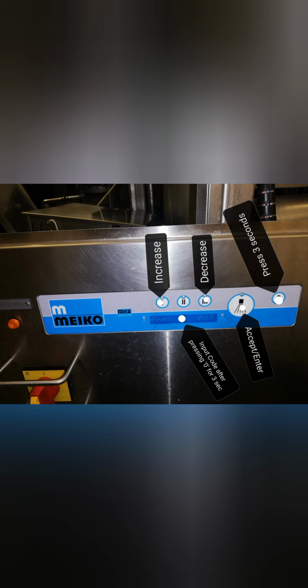So all you have to do is switch on your machine, wait until the first flush, press the 0 for 3 seconds, then choose the code. Since I want to modify the configuration, I put in 20022 and enter on 2-1 to change the configuration I need. Here, you can check the type of machine and model type, and you can adjust the wash temperature setting for where to get ready, and also adjust the rinse time to transfer and the volume of rinse. But of course guys, I listed the original parameters before I changed any, just for reference in case the input parameters won't work.